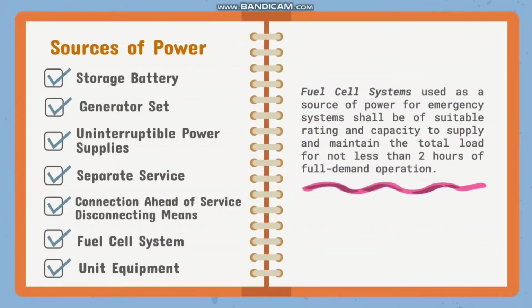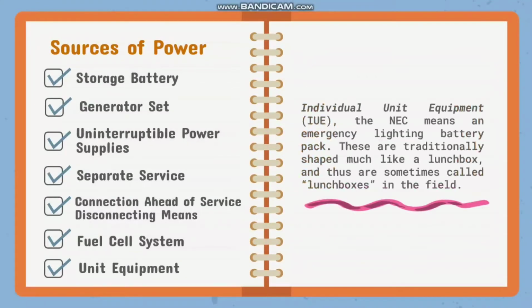Fuel cell systems, used as a source of power for emergency system, shall be of suitable rating and capacity to supply and maintain the total load for not less than 2 hours of full demand operation. For the individual unit equipment, IUE, the National Electrical Code means an emergency lighting battery pack. These are traditionally shaped much like a lunchbox and thus are sometimes called lunchboxes in the field.